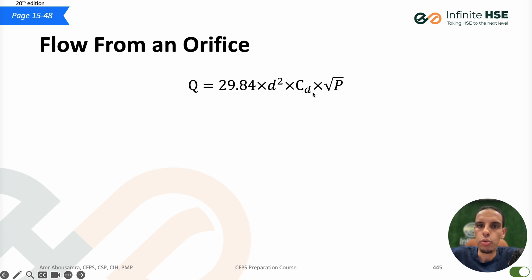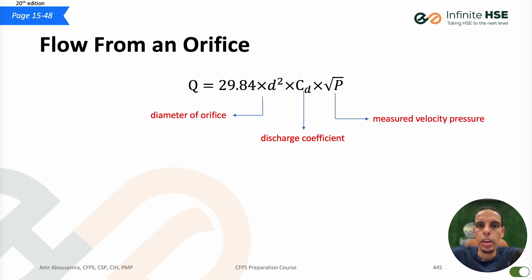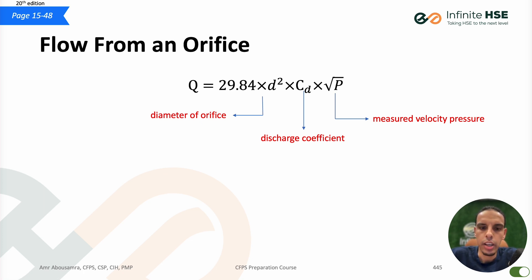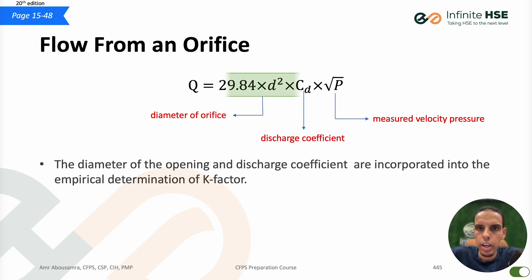As discussed, the equation is Q = 29.84 × d² × cd × √P, where d is the diameter of the orifice and cd is the discharge coefficient, and P is the velocity pressure. Looking at this equation, three components are identical — constant — for each sprinkler or orifice: 29.84 is constant, the diameter is constant for a given orifice, and the discharge coefficient is constant because the material is the same. If we aggregate all three constants together, we get one constant — the k-factor.